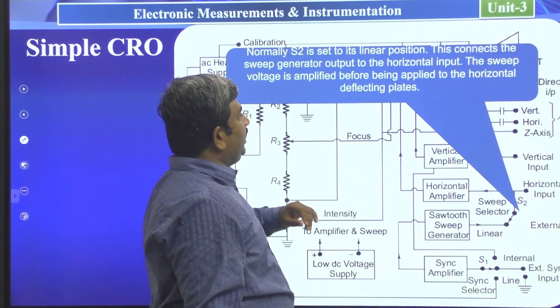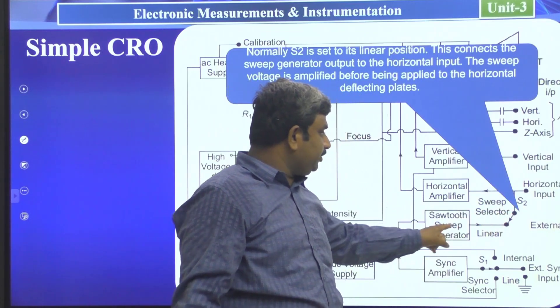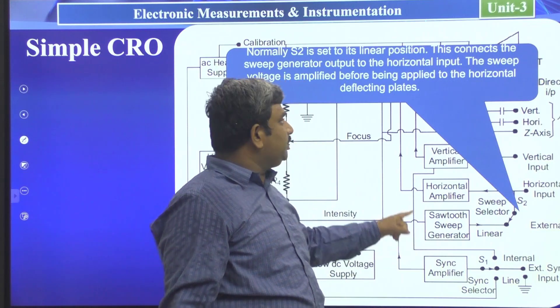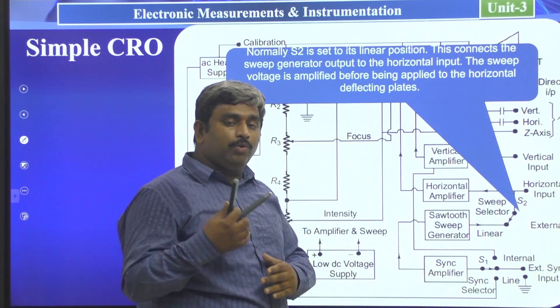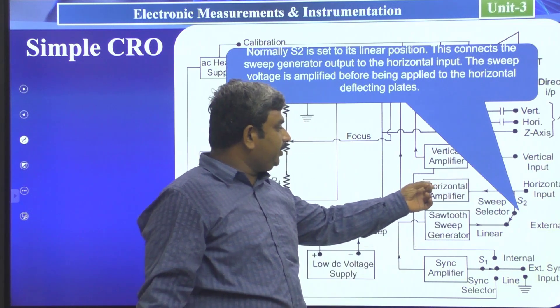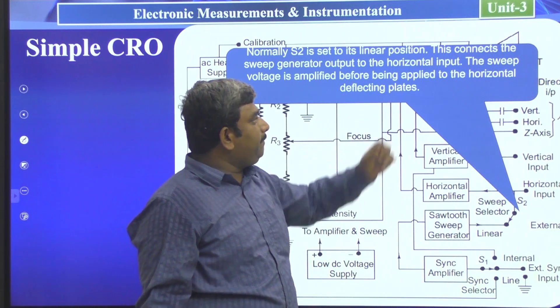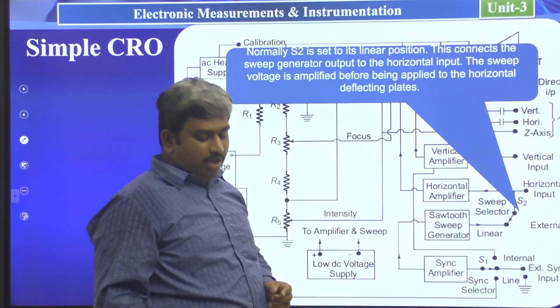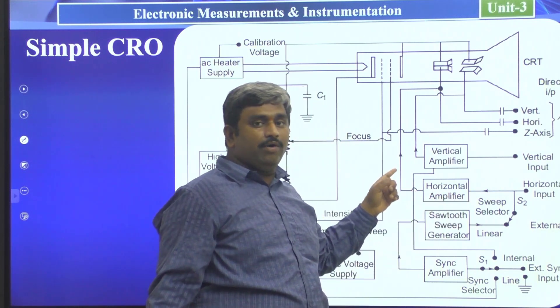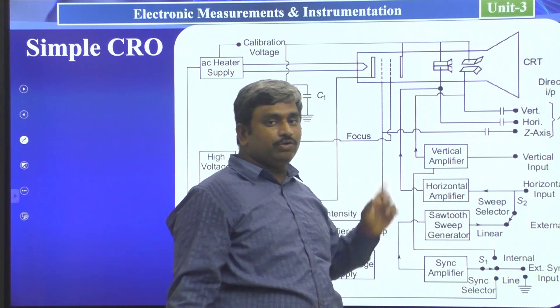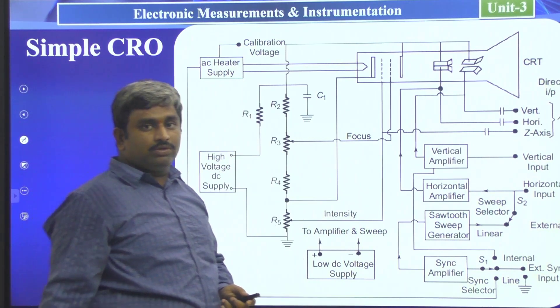Normally, switch S2 is set to its linear position, which connects the sawtooth sweep generator output to the horizontal input. The sweep voltage is amplified by the horizontal amplifier before being applied to the horizontal deflection plates. The sawtooth wave output is connected directly to the horizontal amplifier, which then connects to the horizontal deflection plates.